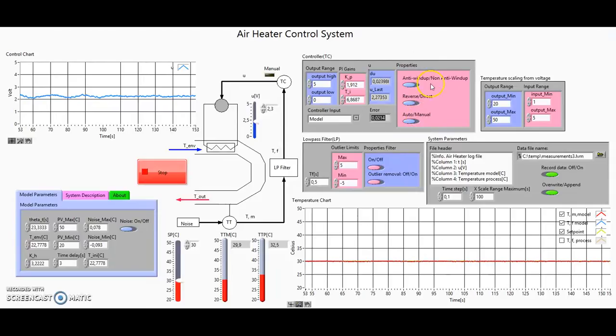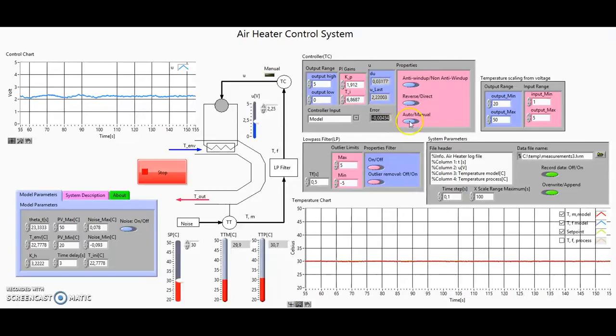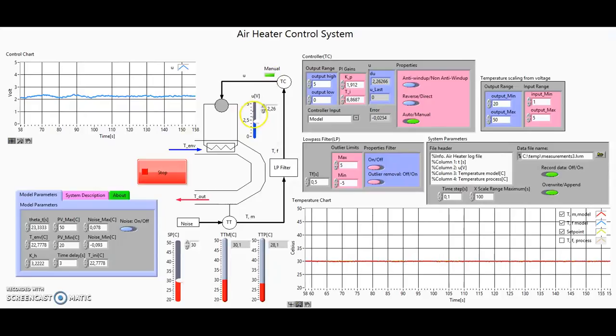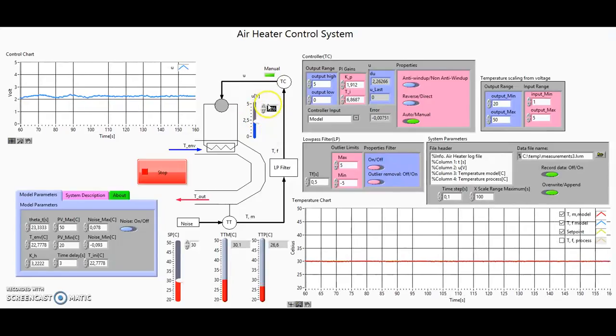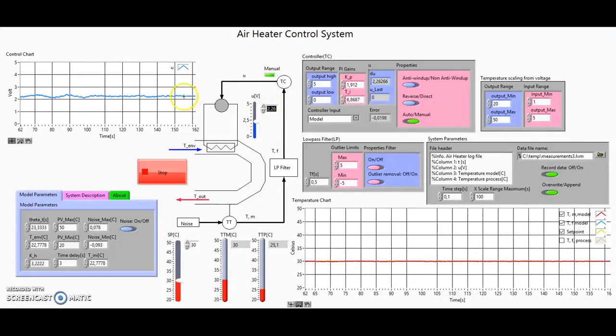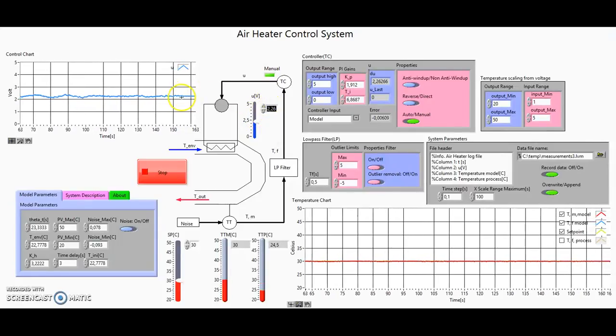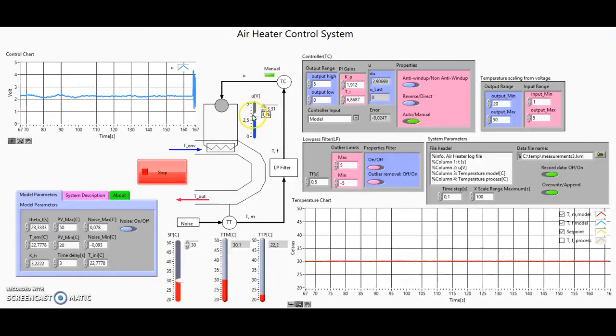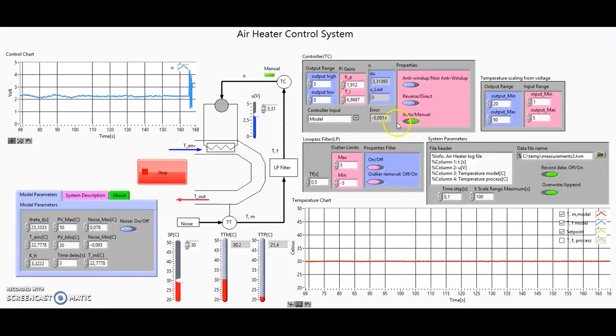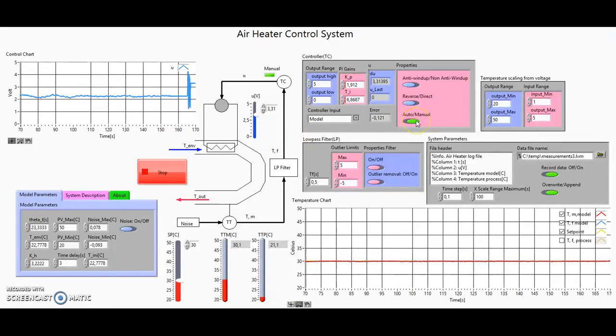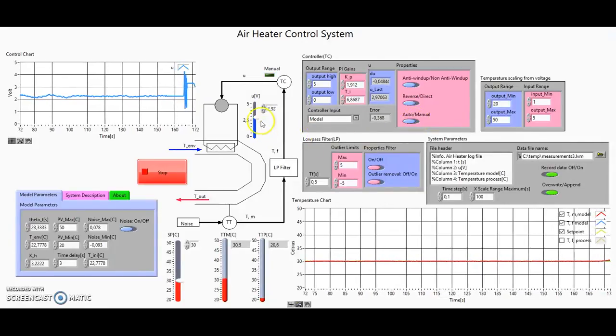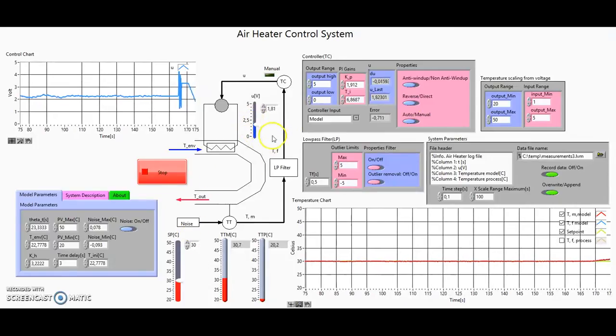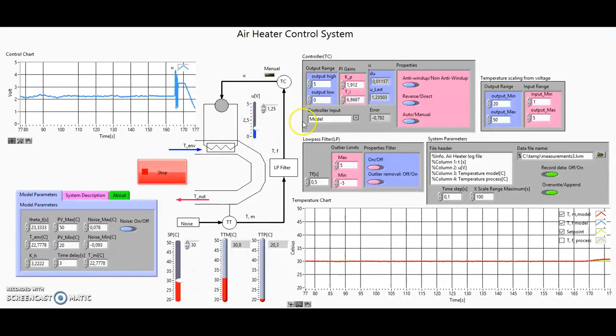Here are some controller properties. You can go from auto to manual — and as you can see, the control value stays the same as it was the last time it was in auto. You can then set the manual value, turn it back to auto, and you get a bumpless transfer back to trying to reach the set point.